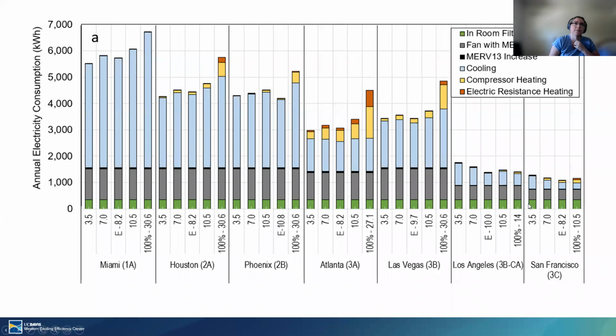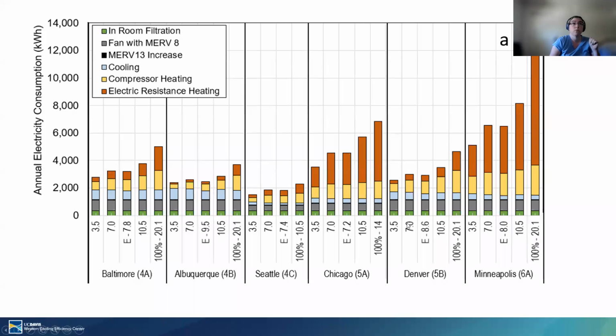I just want to point out, so Los Angeles and San Francisco, those are very interesting cases. In those situations, energy potentially decreases when we increase ventilation, meaning that our cooling loads in our classrooms are quite high and the air outside is so temperate that we can actually get all this extra ventilation in these coastal climates without an energy impact. And so that's important for those climates, right? Because there is a lot of population along the coast. So I think that's an interesting finding. Similar results as we go north and we go east. You can see heating electricity just goes through the roof as we start to increase ventilation rates. And again, what we really see here is that the filtration measures make so much more sense compared to just increasing ventilation.